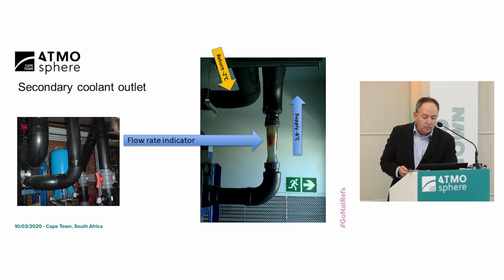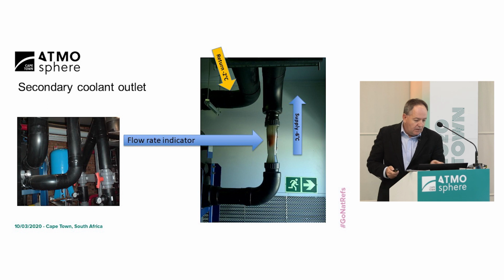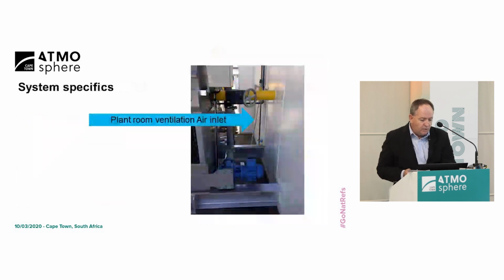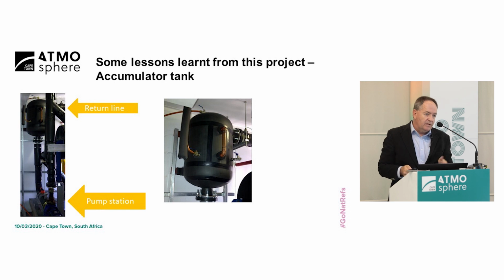You walk in the plant room door, you see that orange float. If it's all the way up, you have maximum flow. If it's down, if there's air in the system, you can see it. Very, very handy to see. That's the inlet to the plant room. A thing we added at a later stage was a makeup tank at the highest point of the system, just to get air out of the system. It's really difficult with a secondary cooling system.